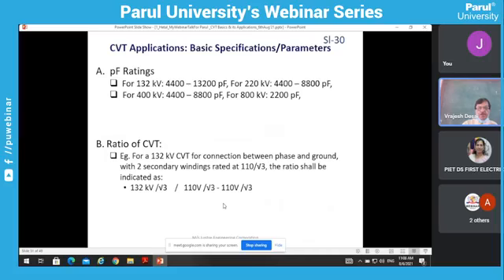PF rating, as I told you, being a capacitor, is always specified by the customers. Normally for 132 kV you can have from 4400 pF to 13200 pF like this, and for 800 kV you can have 2200. Ratio: for example, the primary side is 132 kV by root 3. Root 3 is coming because all these PTs are connected from line to earth, so root 3 always will come. In the same way, the secondary side is 100 volt by root 3.